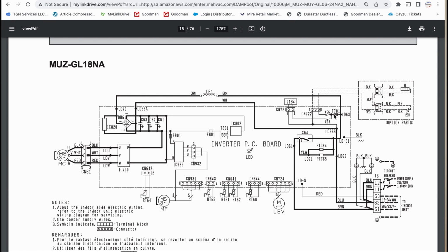Okay. If that fuse is good, then we need to figure out why we don't have voltage at the reversing valve. Okay. And so now that second place that we saw 208, 230 was on LD70 and LD66. Okay. So we would see it right there. If we didn't have voltage here, but we had it down here at L1, L2, then something's going on with our board. Okay. So we would probably have the board bad at that point, because this little relay right here was probably bad. Okay.